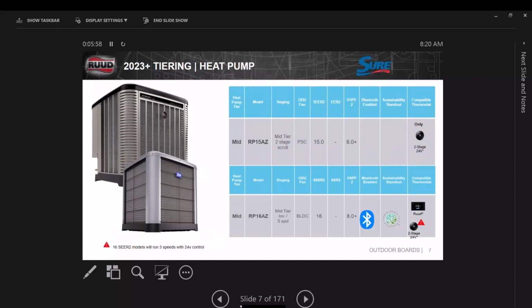Mid-tier heat pumps. Now, notice on the 15 SEER heat pump, remember I said 99% of all the mid-tier stuff is Bluetooth? That is the only one that's not right now. Okay? This unit is a 2-stage scroll compressor, not variable speed, so you would use a regular 2-stage 24-volt thermostat with that. And the setup procedures are the way they were before.